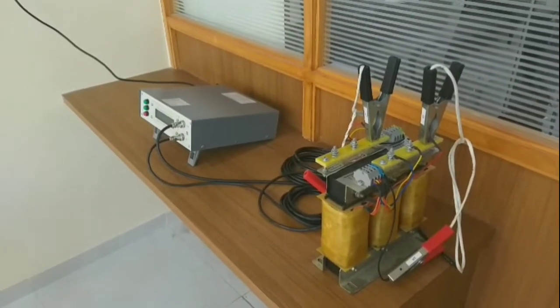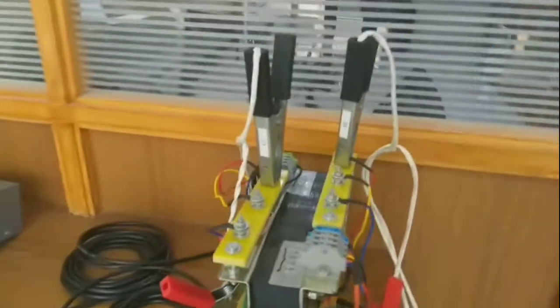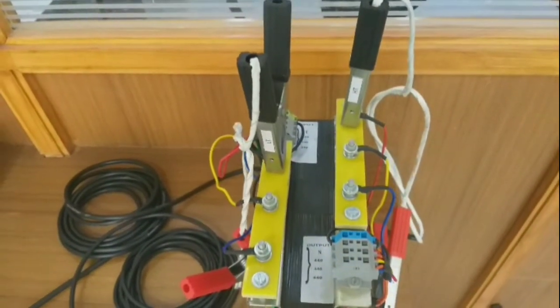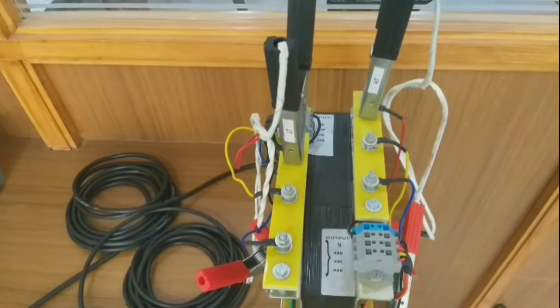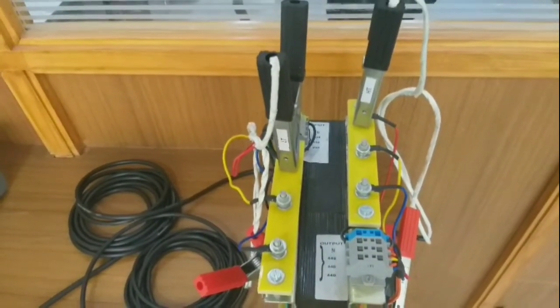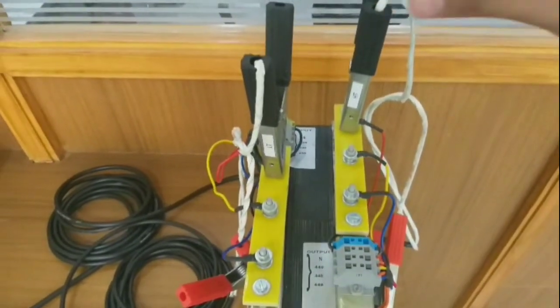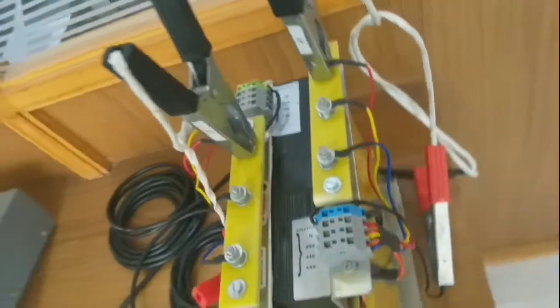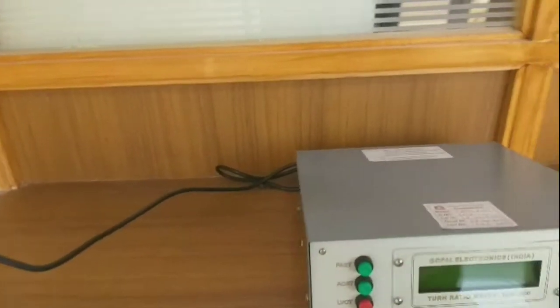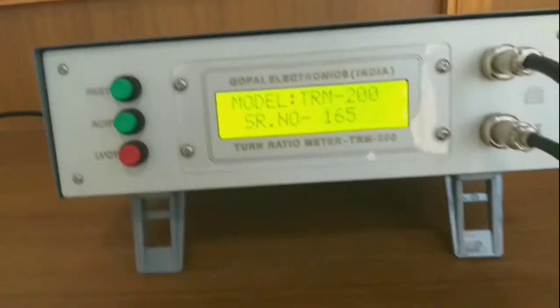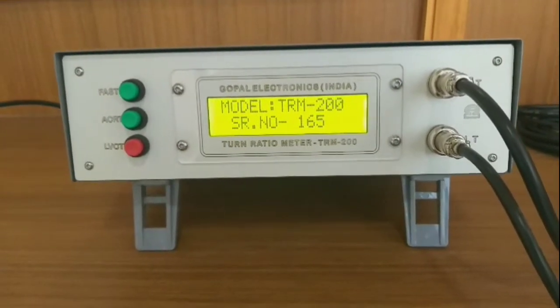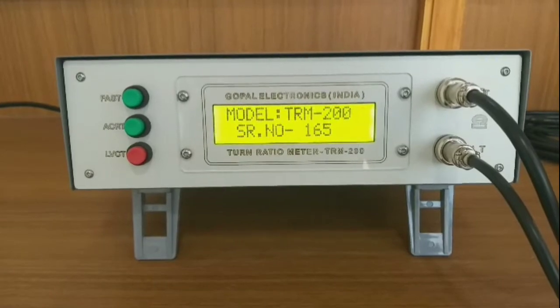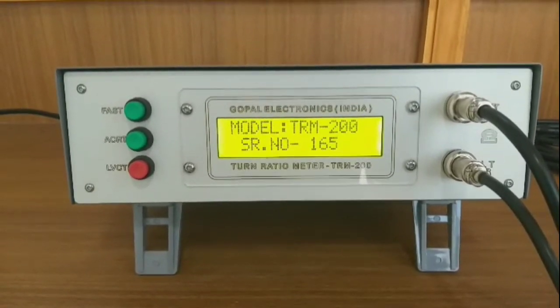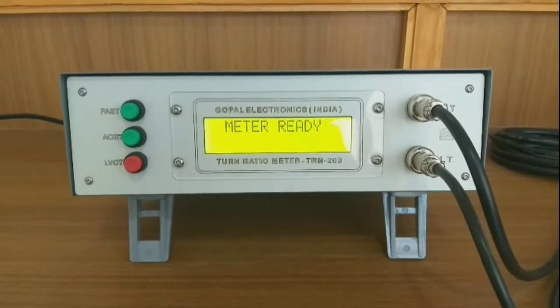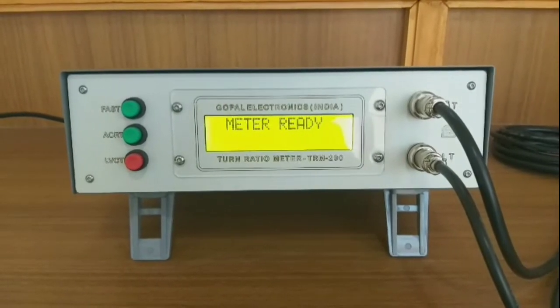I have done all the connections. You can see that I have connected the HT leads on the HT side of the transformer and the LT leads on the LT side of the transformer. First, we will measure the turn ratio of R phase. Therefore, I have connected leads on R phase and another lead on neutral. Now we will turn on the meter. First the meter will show its serial number and then it will be ready. Meter is ready. I will press buttons one by one to show the different modes of testing.